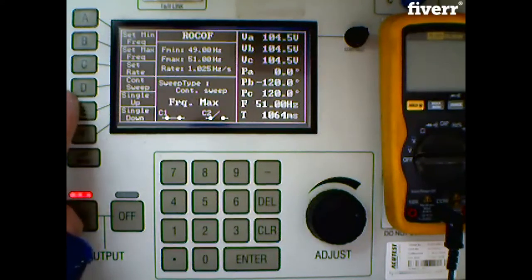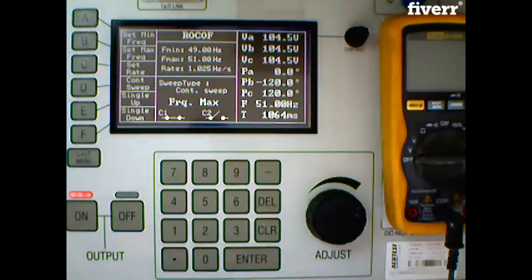Trips at 1064. In my opinion, that is as close as you are going to get it. It's within 39 milliseconds. That's not bad, but you would still have to discuss it with a DNO, and you would still, unfortunately, have to put a fail on your test sheet. That's our first one today, unfortunately. We don't want many of them. I don't like any of them, but we got 1064, and we would have to put a fail.